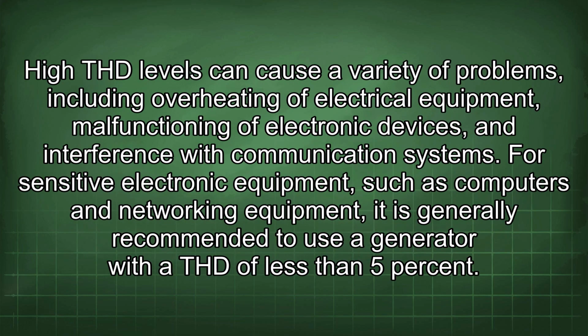High THD levels can cause a variety of problems, including overheating of electrical equipment, malfunctioning of electronic devices, and interference with communication systems. For sensitive electronic equipment, such as computers and networking equipment, it is generally recommended to use a generator with a THD of less than 5%.